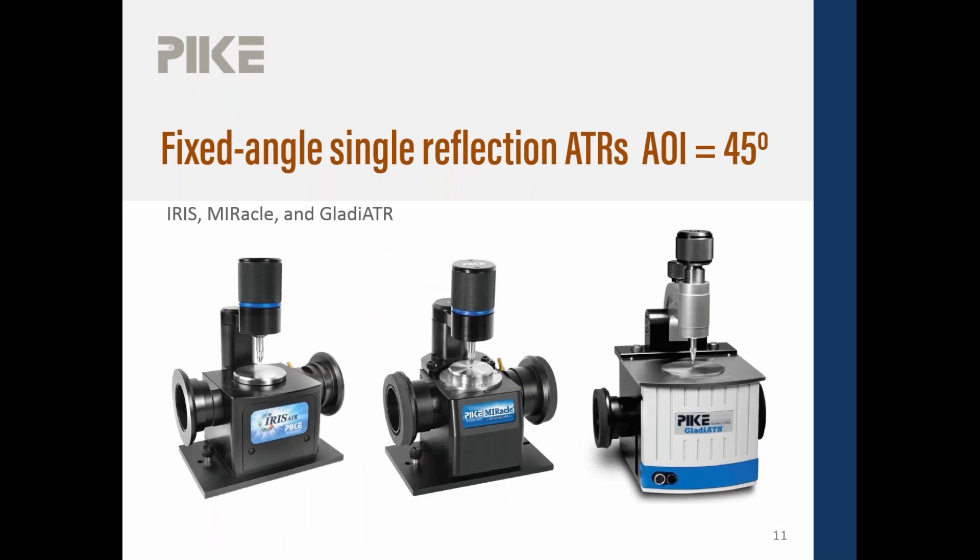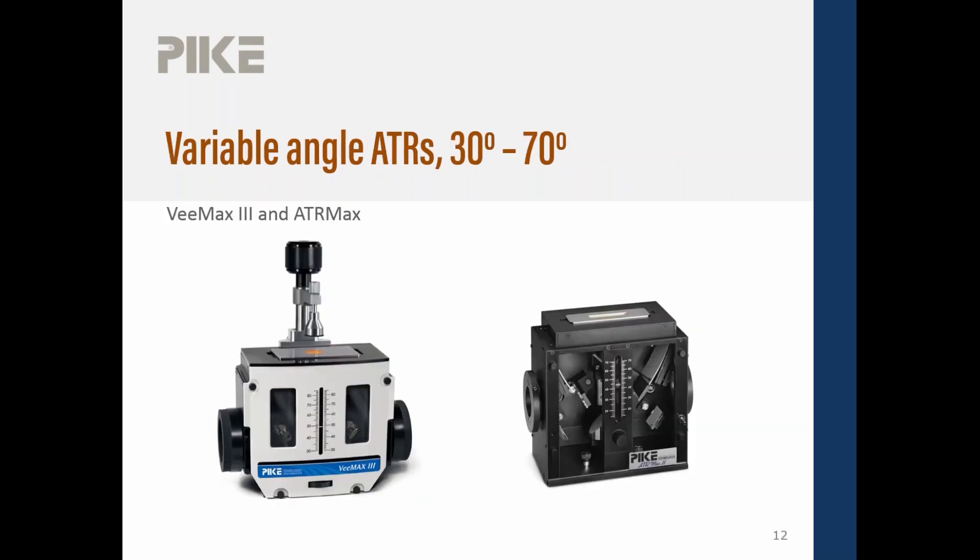So with fixed angle ATRs, probably most of you have these, they're the most popular. Most of you have an ATR in your sample compartment with a little tiny crystal, maybe a diameter of three millimeters or less. Those are going to have an angle of incidence of 45 degrees. I cannot think of any single reflection commercial ATR with a small crystal size that has an angle of incidence that's too far off from 45.